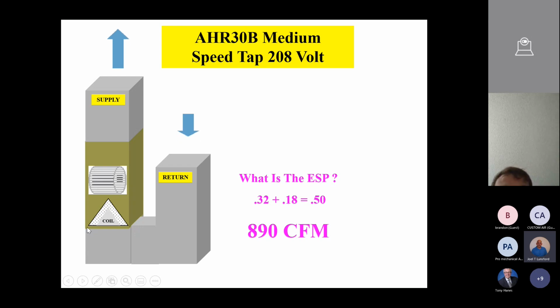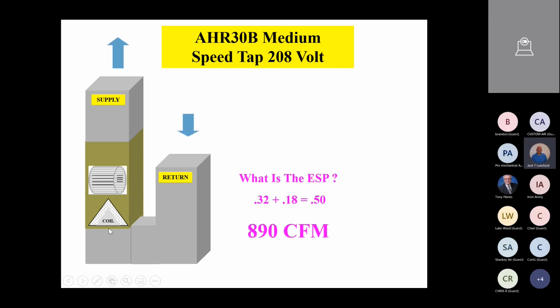Now we didn't talk about it, but there's an alternate probe that works pretty good. It's not as accurate as the static pressure probe I just showed you. It's just a straight piece of tubing. Take a little 1/4 inch or 1/8 inch piece of tubing, poke a hole in the cabinet right between the coil and the filter, and slide that in there, because we want you to read the suck that fan is pulling through the coil and that filter.